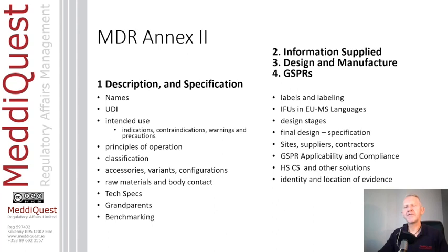In fact, we don't even have any standards that are harmonised under the Medical Device Regulation, so we're having to use standards that were harmonised under the Medical Device Directive as they've been updated, and take the assumption that they are now the state of the art.